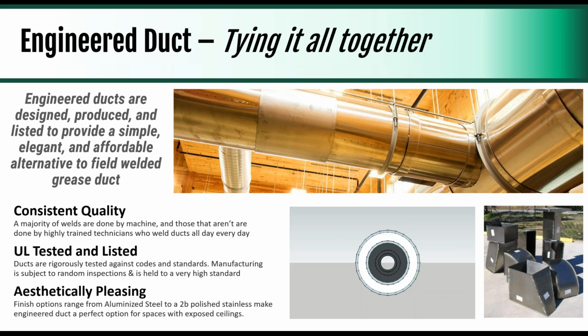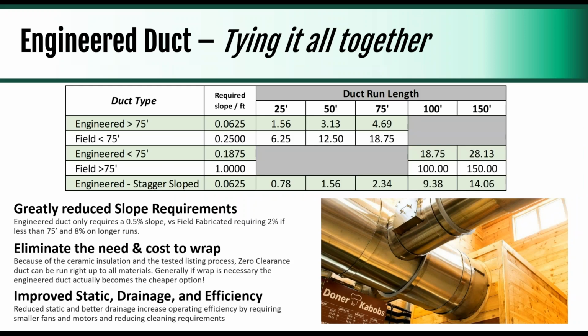Just a quick note. This is actually at the St. Jacobs Farmers Market. It's a really good looking installation, but it's a big open building, nice woodwork everywhere. They decided to go with the engineered ductwork, and it looks great. It's also UL tested and listed, and of a consistent quality. So the welds are all done by machine, not by humans on site, and everything's tested. So it's a really good quality product versus the field fabricated stuff, which is oftentimes good and acceptable, but we've seen it constantly where there are issues with field welded duct.